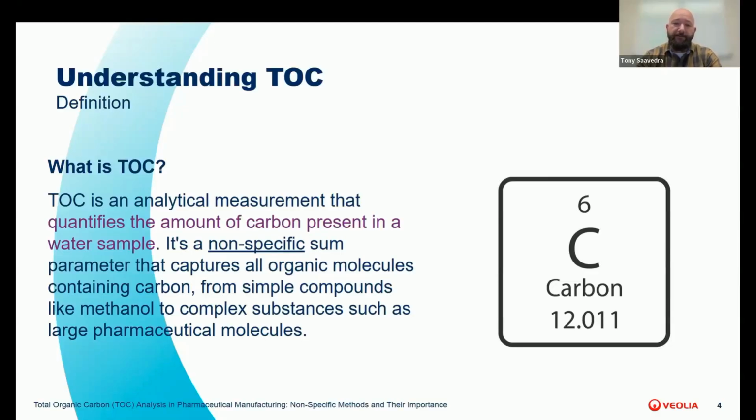Specifically, TOC is the difference between inorganic carbon and total carbon in a sample. The result gives us a number typically expressed in parts per million or parts per billion. It's important to note that TOC doesn't identify specific compounds. Instead, it provides an overall indication of organic contamination or purity in a water sample, making it an invaluable tool in pharmaceutical manufacturing.